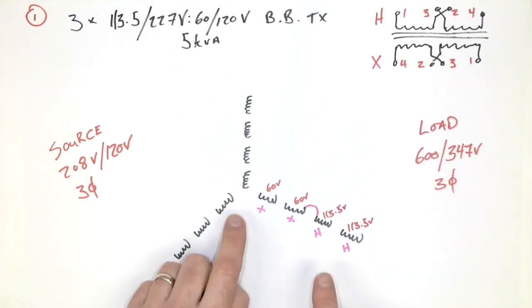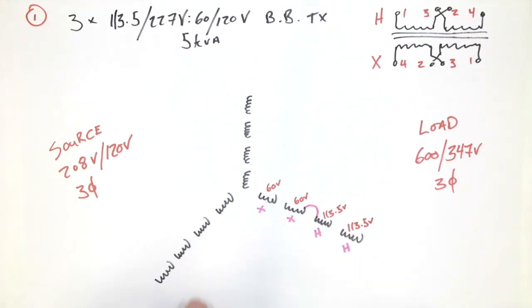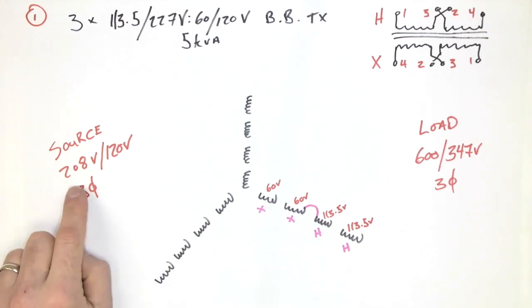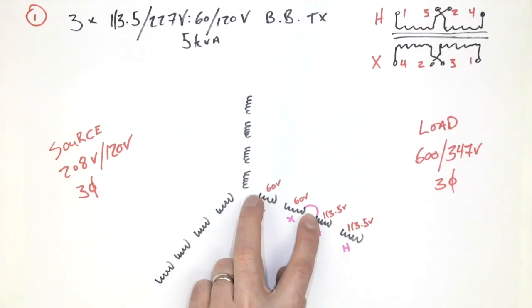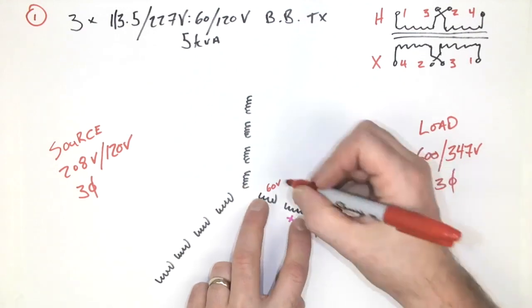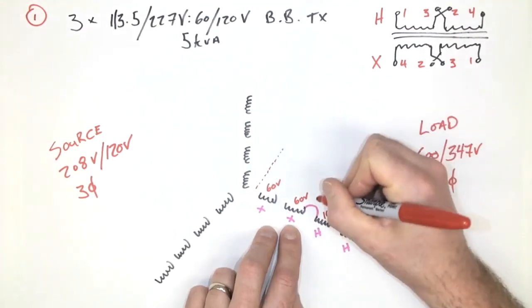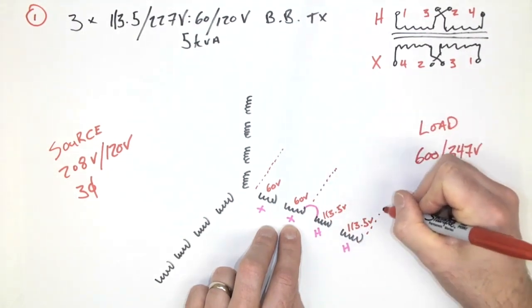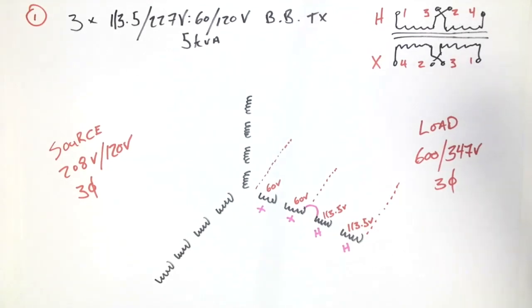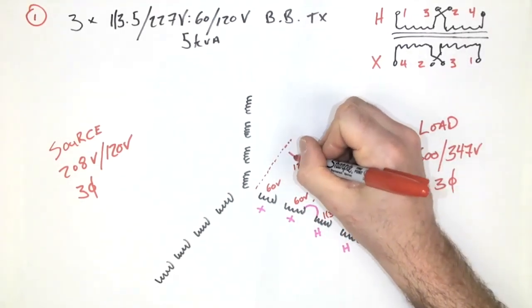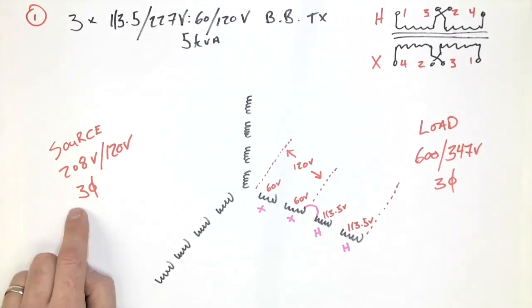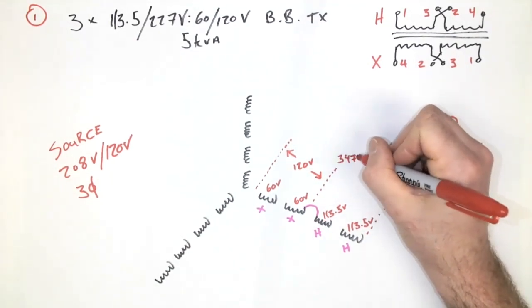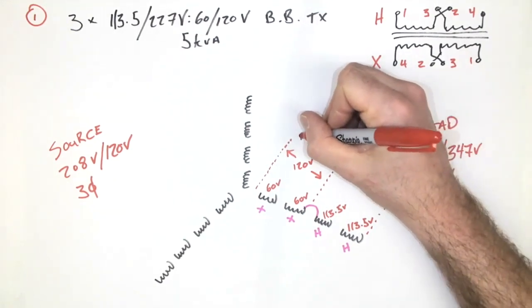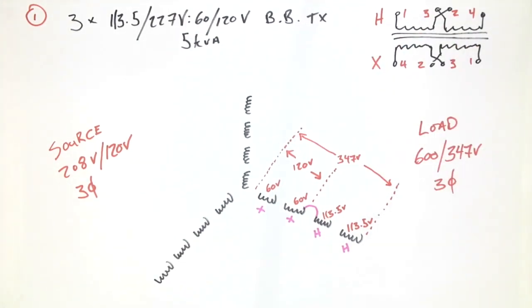Now, the low voltage phase value from here to here has to be 120 volts for our source. The low voltage will be from somewhere in the midpoint to the star. So I'm just going to put a little dotted line here and another dotted line down here. We know that this must be 120 volts. I need 120 volts for my source. And this one from here to here must be 347 volts. I need that for my load. And so based on that information, I can start to piece together what the winding connection must look like.